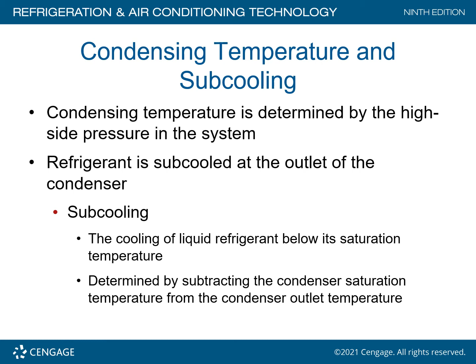Process of subcooling. Okay, so basically we have refrigerant vapor coming from the evaporator coil. Of course, the compressor changes that low pressure, low temperature vapor to a high pressure, high temperature superheated vapor. And notice that the temperature goes up dramatically. We're typically shooting for 125 degrees Fahrenheit across this coil. This basically shows where the first point of liquid takes place. Liquid doesn't start right up here. It starts about down here.